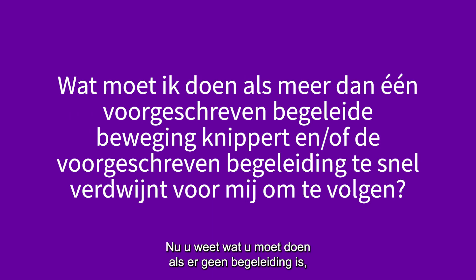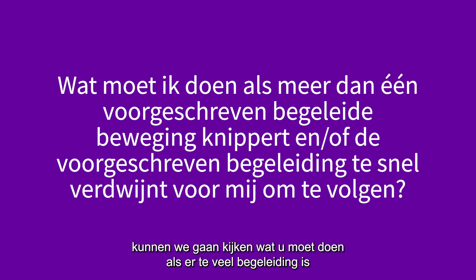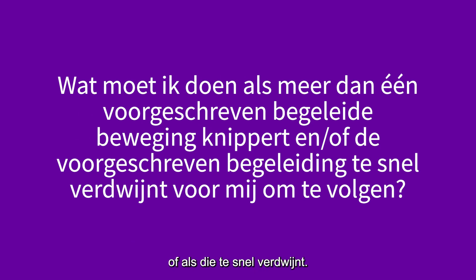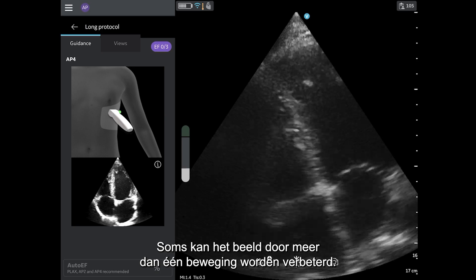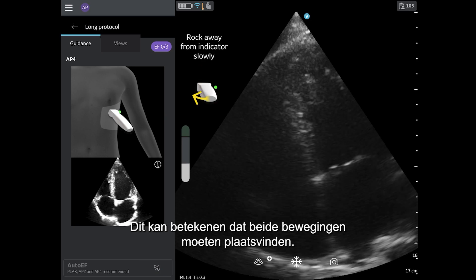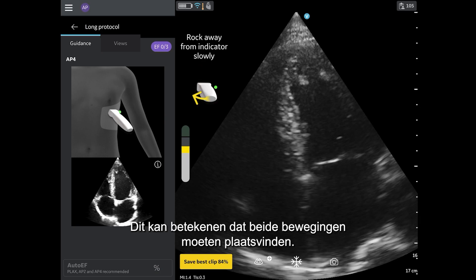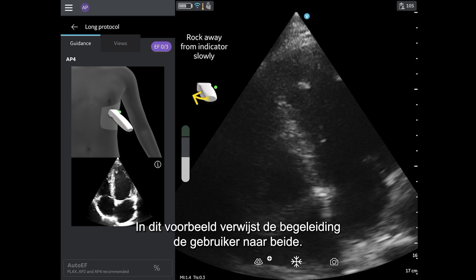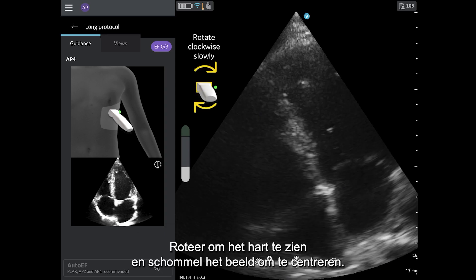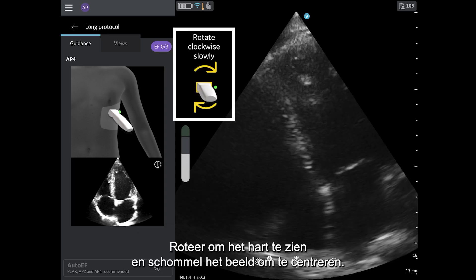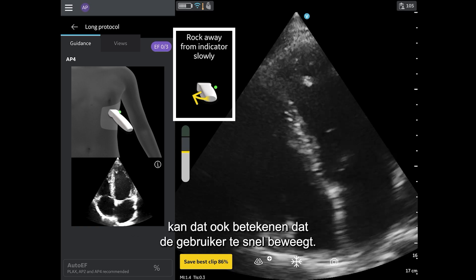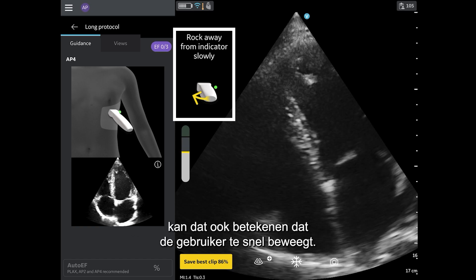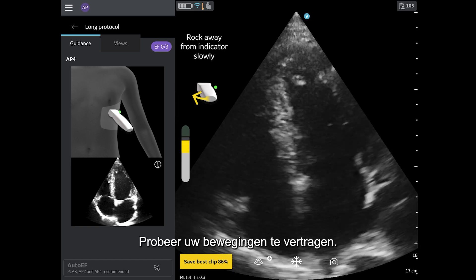Now that we know what to do if there is no guidance, let's review what to do if there is too much guidance, or it disappears too quickly. Sometimes, more than one movement can improve the image. This may mean that both movements need to occur. In this example, the guidance is directing the user to both rotate to see the heart, and rock to center the image. Having multiple movements appear may also mean the user is moving too quickly. Try to slow down your movements.